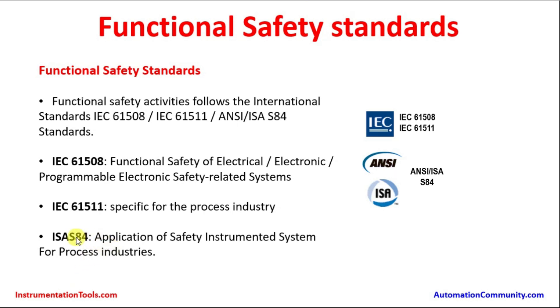ISA 84 covers the application of safety instrumented systems for process industries. IEC 61511 and ISA 84 are for the process industries, while IEC 61508 is for the manufacturers who make products for the safety instrumented system — such as sensors, logic solvers, or final control elements. All components within these three categories — sensor, logic solver, and final control elements — have to be certified and must follow the IEC standards.